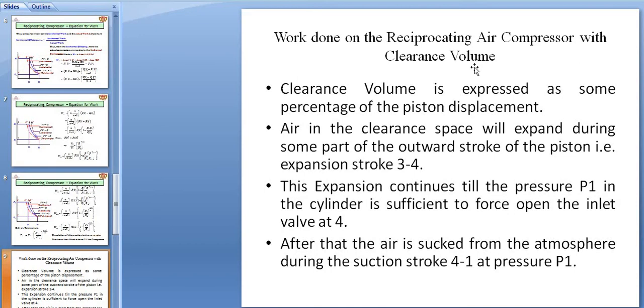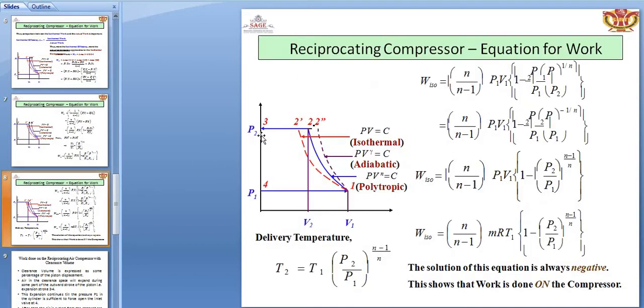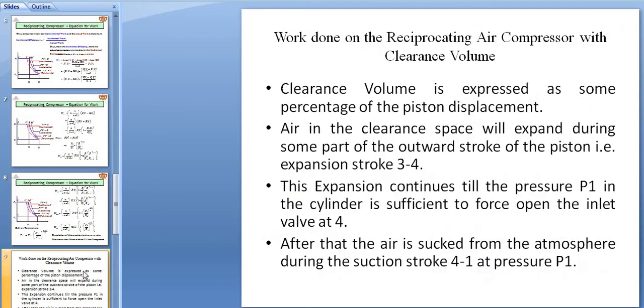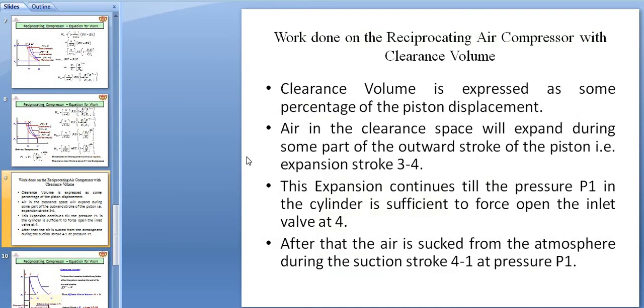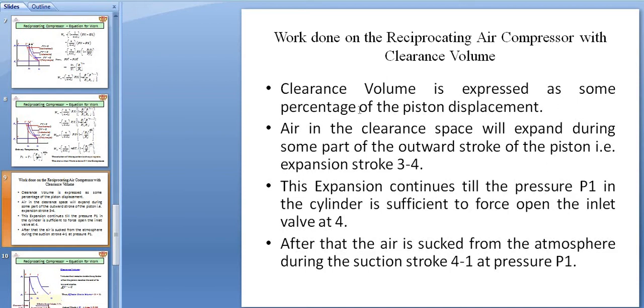Work done on the reciprocating compressor with the clearance volume — now the clearance volume is considered. In the previous slide, clearance volume was zero, but now it must be considered because the piston cannot touch the cylinder head directly; clearance space is always maintained. The clearance volume is expressed as a percentage of the piston displacement. Air in the clearance space will expand during part of the return stroke.